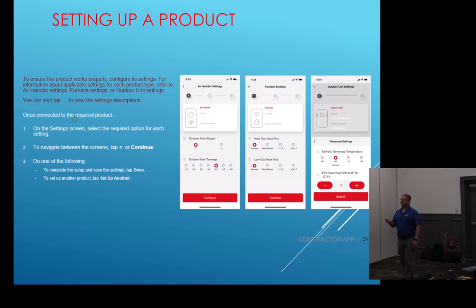Okay? Defrost termination temperature. You can change that. EXV superheat offset. This is only going to be on the 18 SEER units because our 15 and 16 have TXVs. All right? Only the 18 has an EXV. But I will tell you this. If you feel the need that you need to change this because you can't get your temperatures or pressures right, before you change this, call me. Because even on the old 17s and 20s, you used to change it on a little board that we had on the coil, a little microprocessor board on that coil, and it was usually not the board that you needed to change. It was either charge, TXV, or airflow related is why we couldn't get the superheat that we were looking for. Okay?